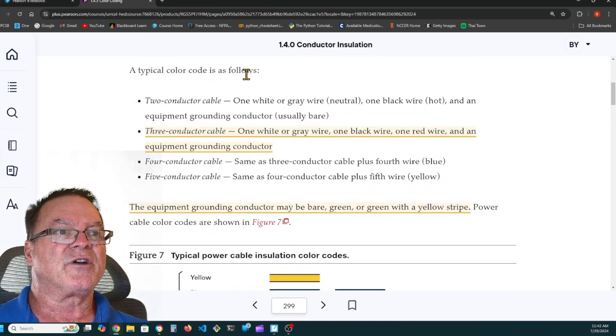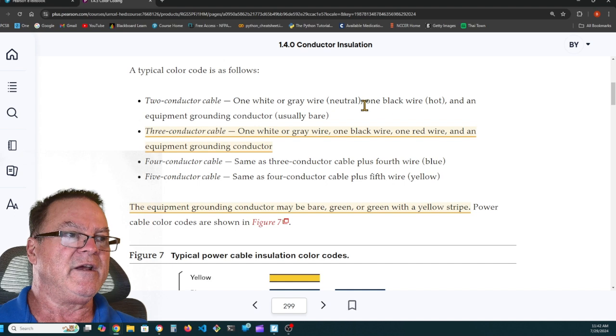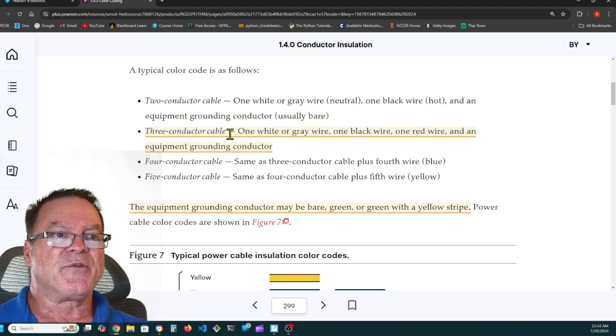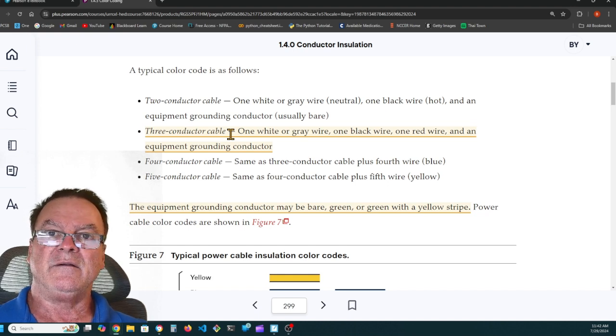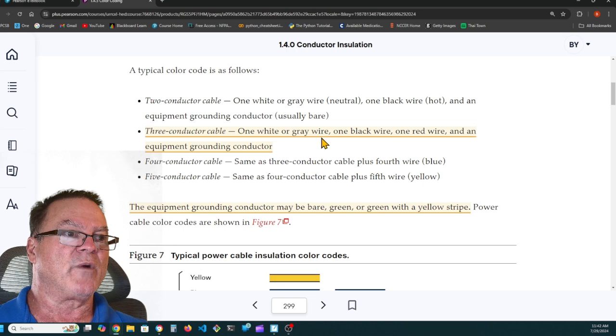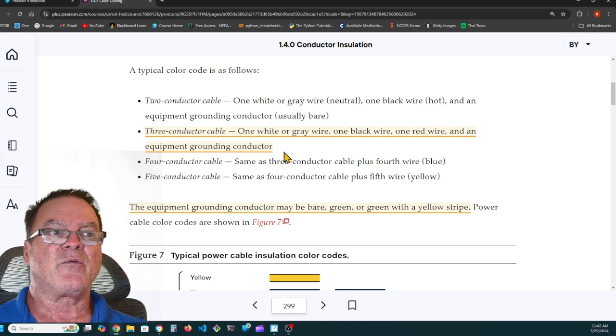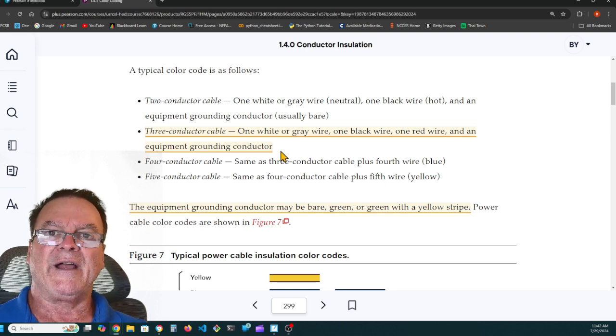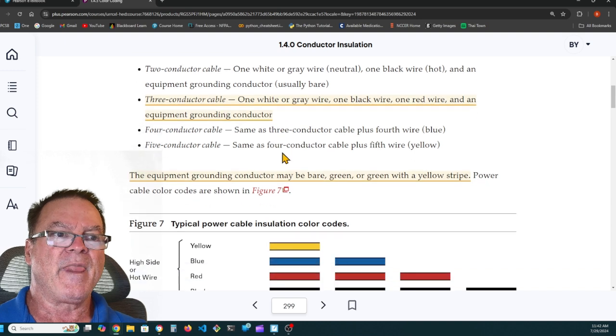So a typical color code is as follows. 2 conductors will be black, white, and a green. 1 white or gray, 1 black wire, and an equipment grounding conductor. 3 conductor cable, and this is highlighted, will be black, red, white, and green. So 1 white or gray, 1 black wire, 1 red wire, and an equipment grounding conductor. So it's black, white, ground, black, red, white, ground.